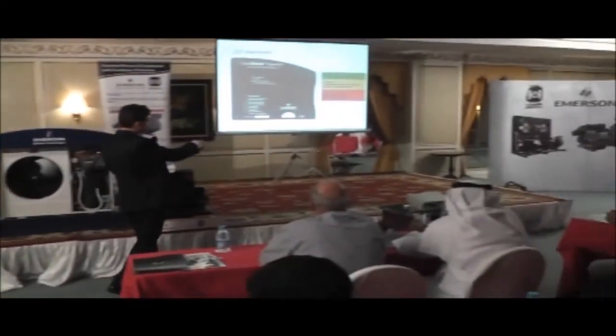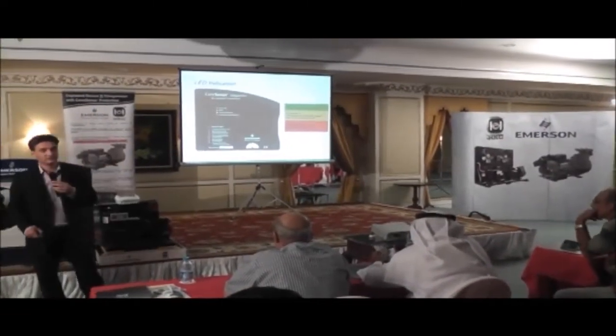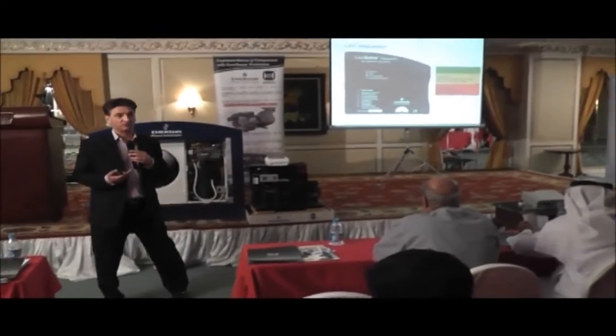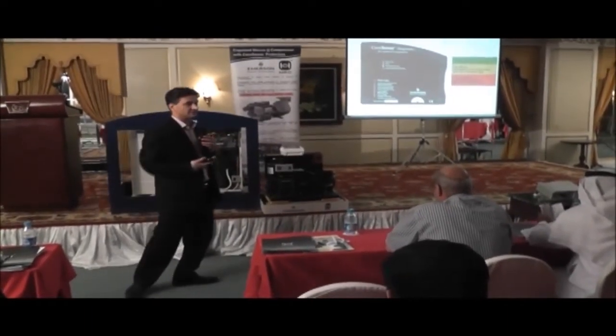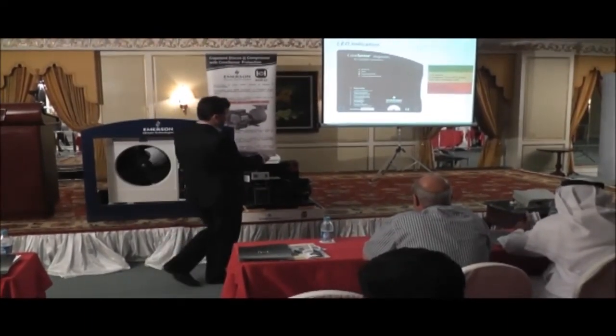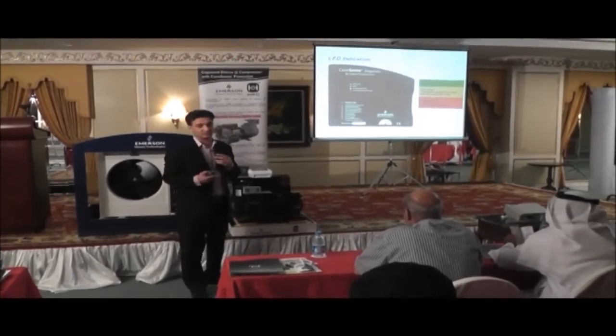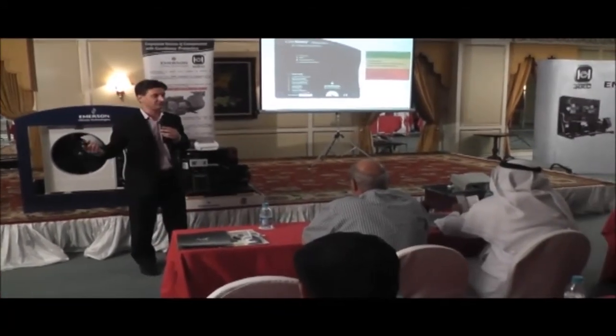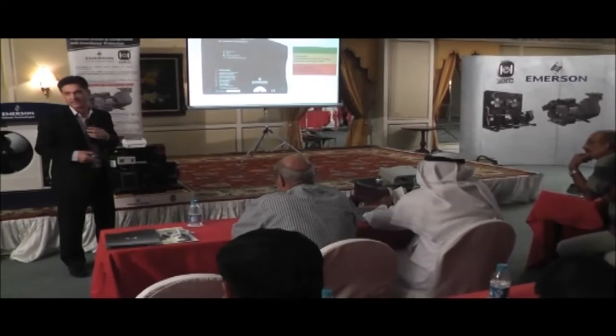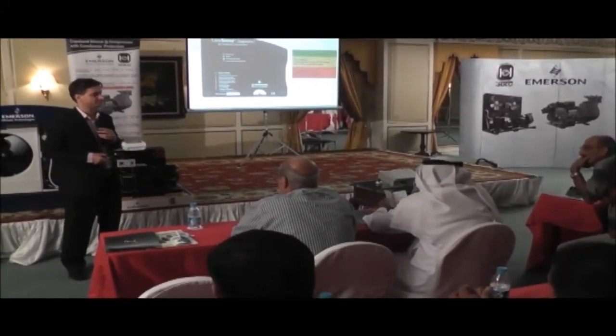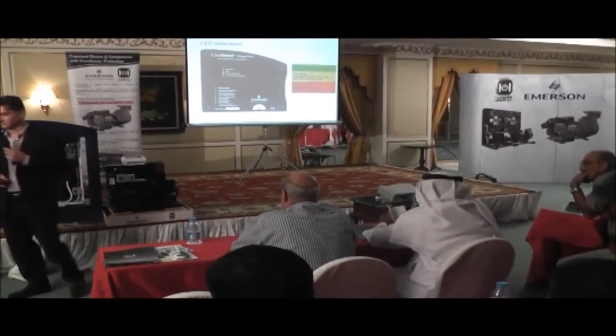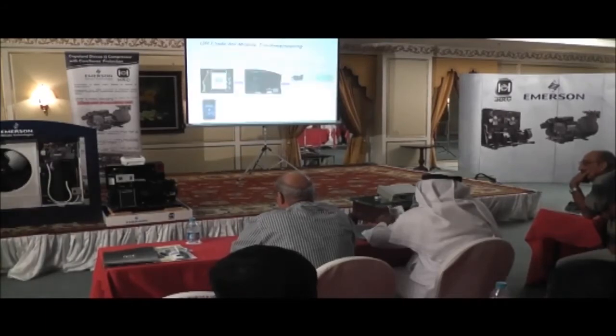This is the reset button on the module. It's located at the bottom end here. Okay. So once you've identified what problem you have, done the repairs to the system, you can reset. The compressor will then get rid of that manual lockout feature that it has, and it will try and start again. All right? Pretty simple.